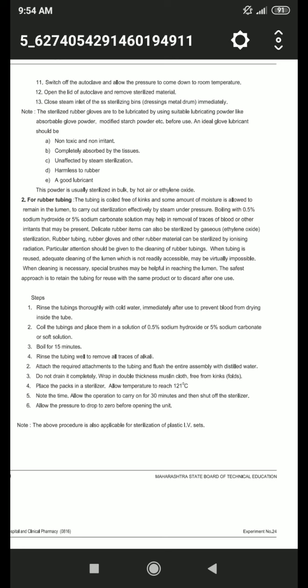First, rinse the tubing thoroughly with cold water immediately after use to prevent the blood from drying inside the tube. Then coil the tubing and place it in a solution of 0.5% sodium hydroxide or 5% sodium carbonate soft solution. Then boil for 15 minutes. Then rinse the tubing well to remove all traces of alkali. Then attach the required attachment to the tubing and flush the entire assembly with distilled water. Do not drain it completely. Wrap in double thickness muslin cloth, free from kinks or folds. Then place the packs in the sterilizer, allow the temperature to reach 121 degrees Celsius, note the time, and allow the operation to carry on for 30 minutes, then shut off the sterilizer. Then allow the pressure to drop to 0 before opening the unit. Note that for rubber tubing, the above procedure is also applicable for the sterilization of plastic IV sets.